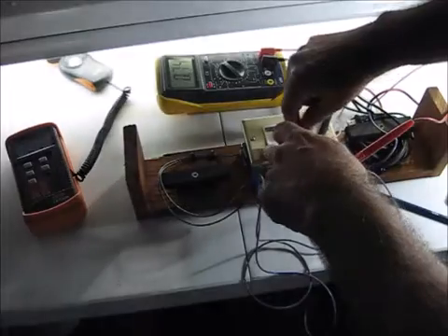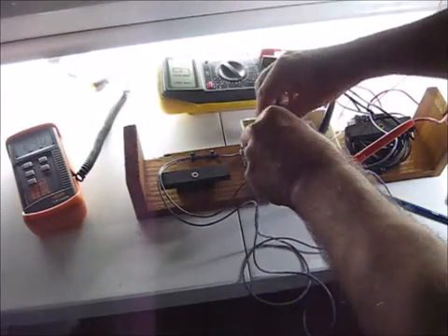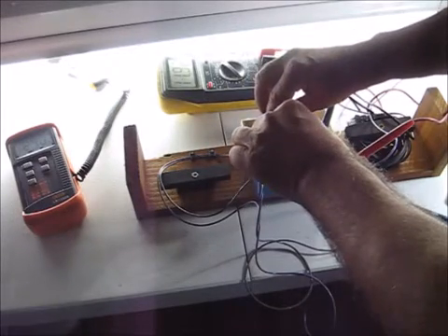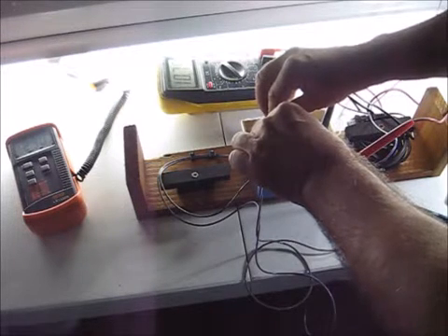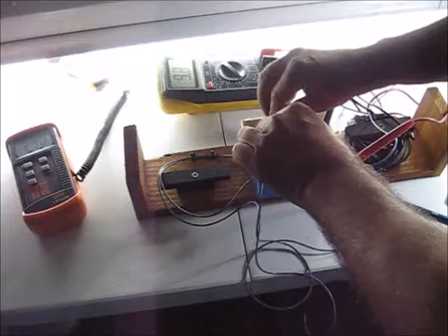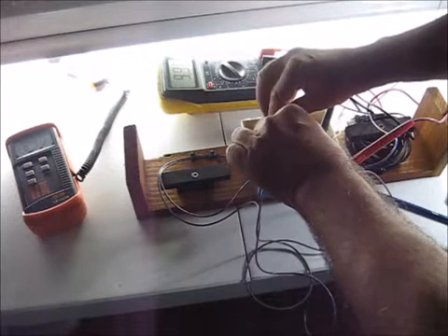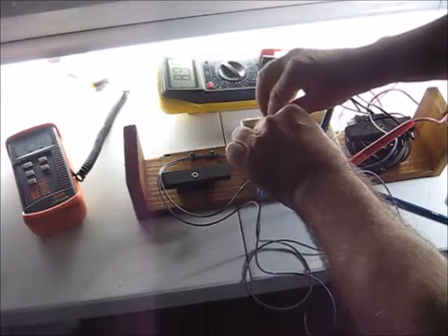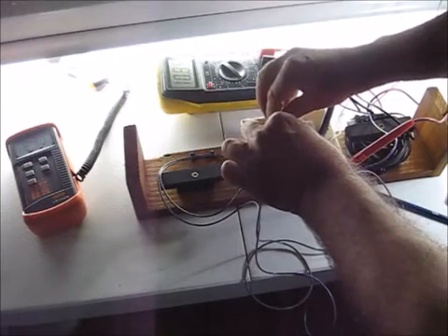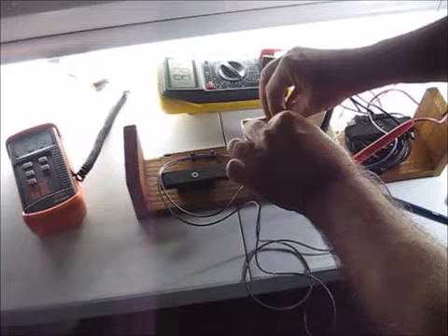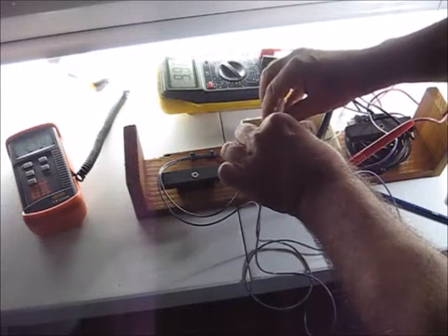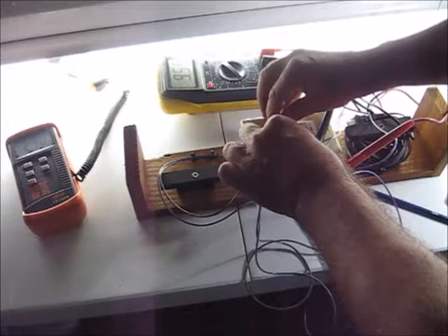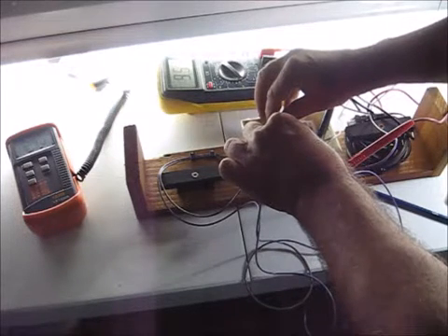There is some delay built into the ballast for the dimming. So you have to pick around kind of carefully. At 10.75, we're still all the way up. At 9.9, we're still all the way up. I think that we're seeing, it's really twitchy as usual. There's just 9.92, 9.5 or so, still all the way up.